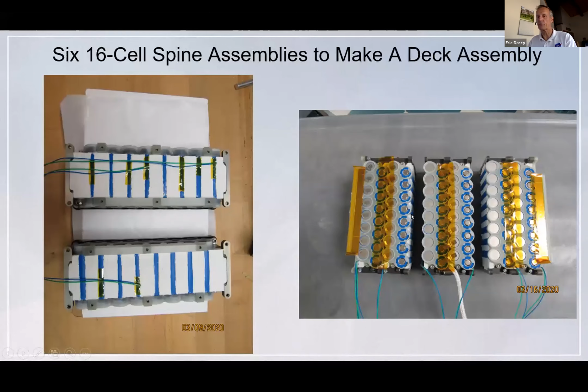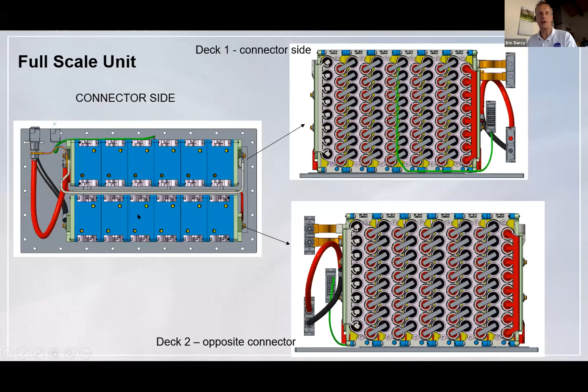So we put these two decks together into one box. They're in series for a 100-volt battery pack, 2 kWh. And in order to trigger thermal runaway, we use the NASA NREL internal short circuit device, which is embedded inside the cells and has a wax layer that melts at 57 degrees and produces a hard short due to the winding tension that's in the jelly roll.